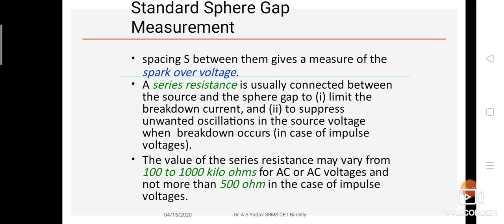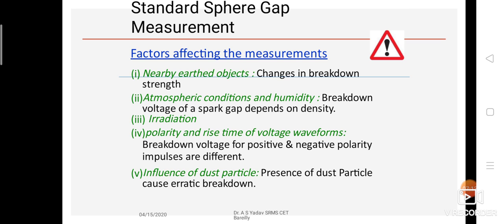The series resistance is usually connected between the source and the sphere gap to limit the breakdown current and to suppress the unwanted oscillations in the source voltage when breakdown occurs in the case of impulse voltage. The value of series resistance may vary from 100 to 1000 kilo ohm, and not more than 500 ohm for impulse voltages. The factors affecting the sphere gap method are nearby earthed objects, atmospheric condition and humidity, irradiation, polarity and rise time of the voltage waveform, and the influence of dust particles.